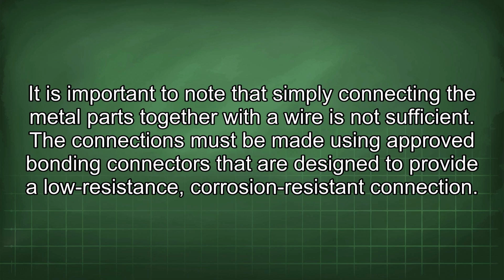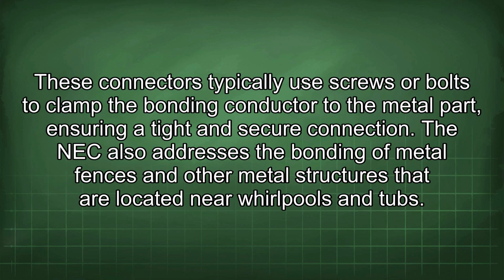It is important to note that simply connecting the metal parts together with a wire is not sufficient. The connections must be made using approved bonding connectors that are designed to provide a low-resistance, corrosion-resistant connection. These connectors typically use screws or bolts to clamp the bonding conductor to the metal part, ensuring a tight and secure connection. The NEC also addresses the bonding of metal fences and other metal structures that are located near whirlpools and tubs.